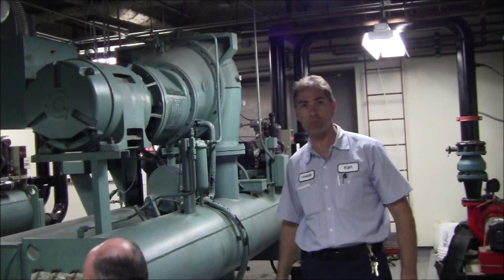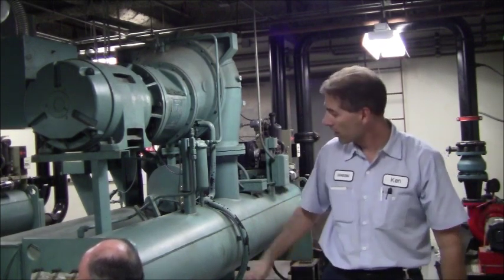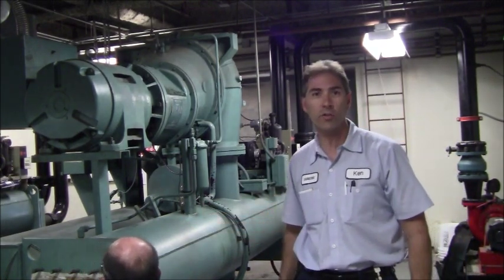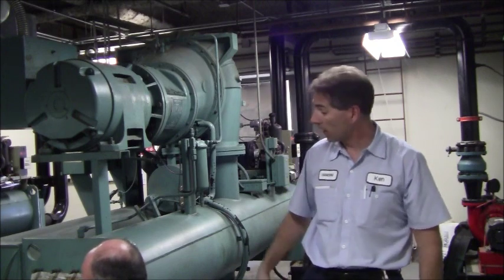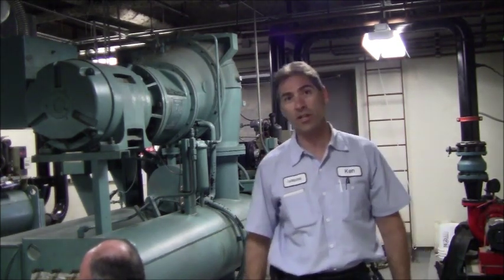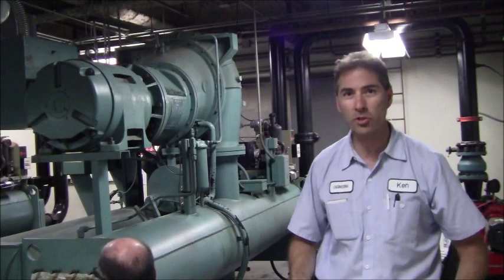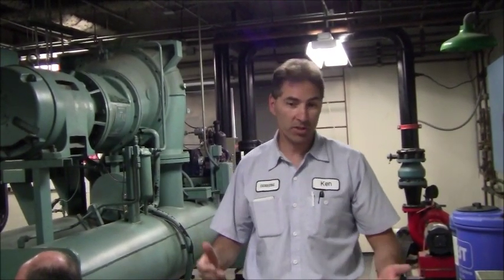This particular chiller, which is running R11 refrigerant, is a little over 26 years of age. So we're performing an eddy current test here to see how the tubes are doing at 26 years of age. How many more years can we get out of these tubes and out of this chiller? And what is the life expectancy of the chiller? Some people say life expectancy is 25 years, so we're already at that life expectancy. But you can push that out with good maintenance and repairs and so forth.